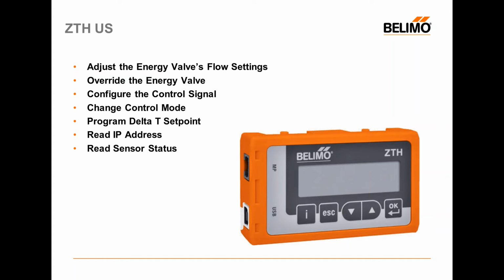So this is a small gateway that has a 2-line LCD display. Some of you may recognize this device if you've used the Belimo PC tool. This is the gateway to use PC tool to connect to an MFT actuator as well. But here you can simply take the cable provided, plug it directly into the actuator on the energy valve. It will power up the ZTH-US. The ZTH will discover the energy valve, and then you can go through and make some adjustments to the valve settings. You can override the energy valve, change control signal or mode.